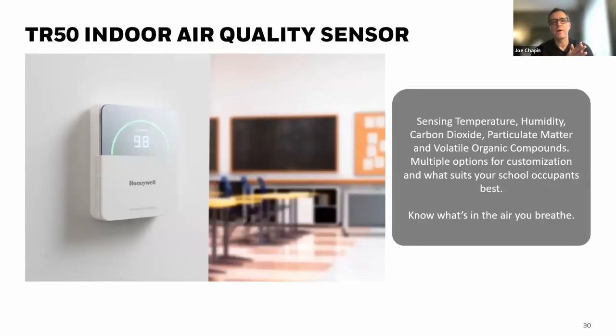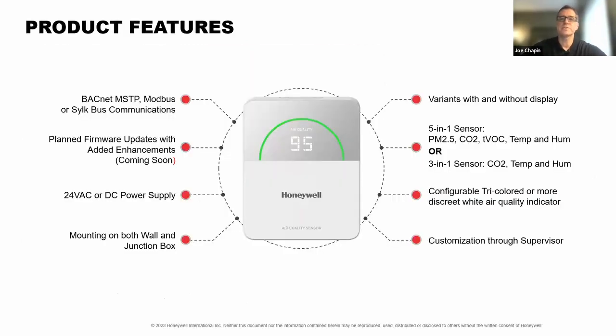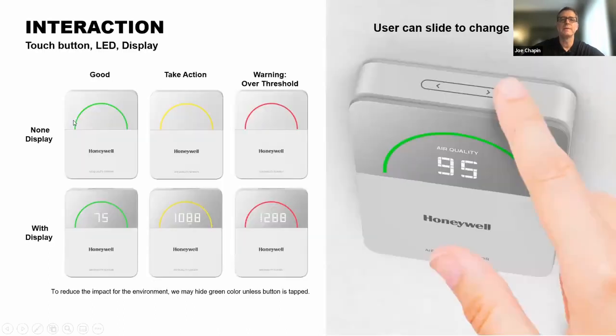Let's talk briefly about one of the sensors that was on the slide before. This is our TR50 IAQ sensor. You can do humidity, temperature, particulate matter, VOC, and there are two different flavors. On the right-hand side, you have the 5-in-1 sensor: PM2.5, that's particulate matter 2.5, CO2, total volatile organic compounds, temperature and humidity. Or you have a 3-in-1 version, which is CO2, temperature, and humidity. This is a single device with multiple sensors and different parameters you can read out, connecting to a building system via BACnet MS/TP, Modbus, so multiple communication methods for flexibility.